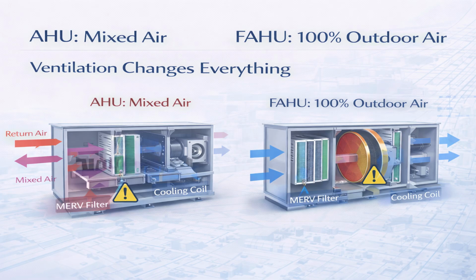An AHU typically handles mixed air, a combination of return air from the space and a portion of outdoor air for ventilation. Because a larger part of the air has already been conditioned, the thermal and moisture loads are relatively moderate. A FAHU, on the other hand, handles 100% outdoor air. This single difference changes everything. Outdoor air carries significantly higher latent load, especially in hot and humid climates. As a result, FAHUs require very different design considerations.